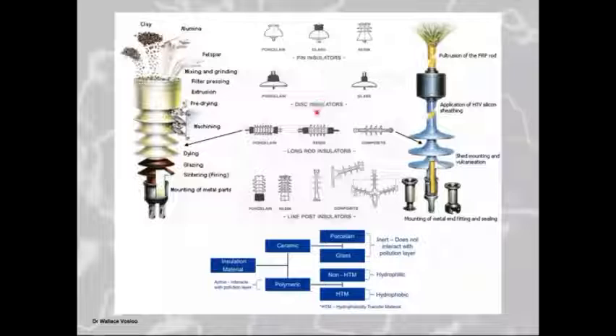Then the disc insulators could either be porcelain or glass, and that's where you have a glass disc, which is basically made in the factory from a glob of glass, which is then pressed in between two shaping presses, and then out comes this disc. This disc has a high tension on the surface, which makes it quite strong. When you break the disc, it shatters like a windscreen because it's tempered glass. And then on this disc, they put a cap with cement at the top, and they put a pin with cement at the bottom, and it sets. And then this cap and pin disc insulator is formed. Mechanically, you can't pull out the pin because it pushes towards the side, and then basically the forces work against one another, which keeps the pin in. And you normally find that it's either a tongue and clevis or a ball and socket.